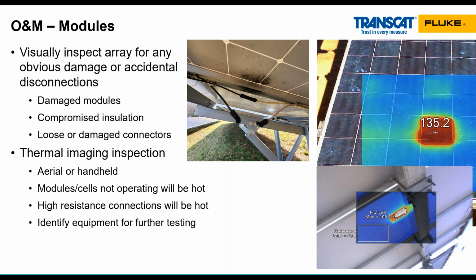Beyond a visual inspection, using thermal imaging can find a lot of problems that you can't see with a visual inspection. For example, this is a cell that has a problem. I was actually in the field last week and saw this very problem. In the case that I was in, that cell had been damaged for some time, and you could visually see that the cell was burnt out on the front of the module. When you looked at the back of the module, the back sheet was actually burnt up and charred right where that cell is. In the early stages of a problem like this, you would not see that with a visual inspection, but you can very clearly see it with a thermal imaging camera.